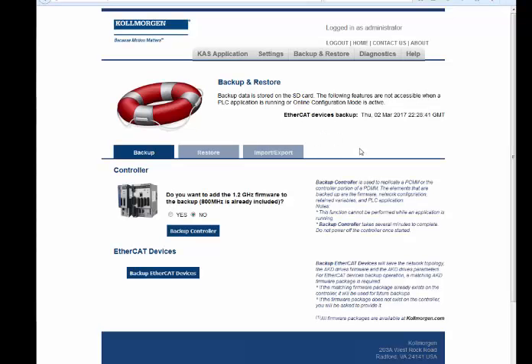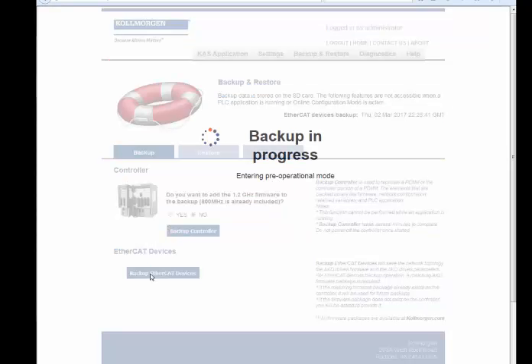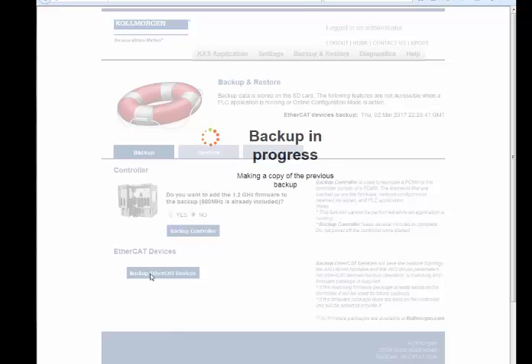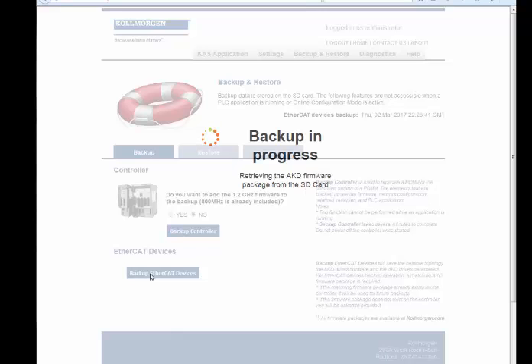EtherCAT devices discovers all items on the EtherCAT network and backs up network topology information, AKD firmware files, and AKD parameters to the SD card. A matching AKD firmware package is required to complete the backup. If the matching firmware package already exists on the controller, it will be used for future backups. If the firmware package does not exist on the controller, you will be prompted to provide it.